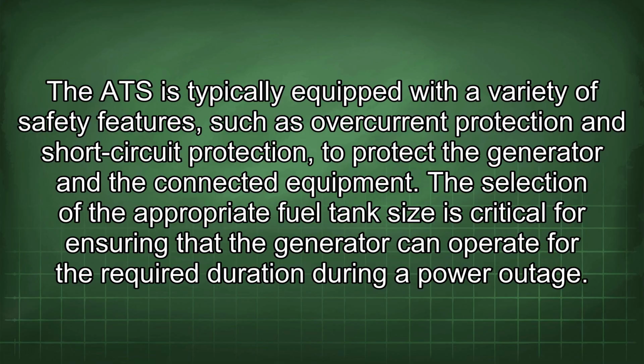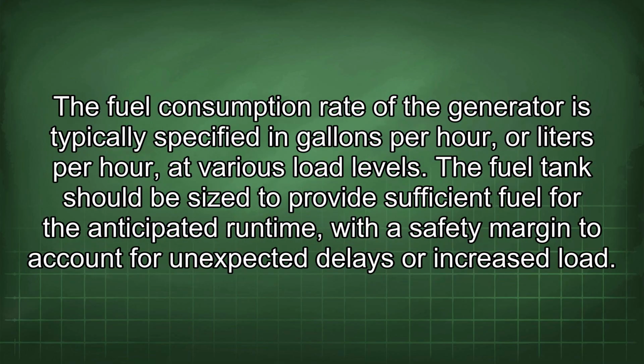The selection of the appropriate fuel tank size is critical for ensuring that the generator can operate for the required duration during a power outage. The fuel consumption rate of the generator is typically specified in gallons per hour or liters per hour at various load levels. The fuel tank should be sized to provide sufficient fuel for the anticipated runtime, with a safety margin to account for unexpected delays or increased load.